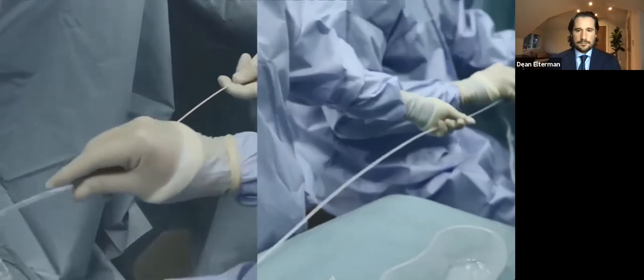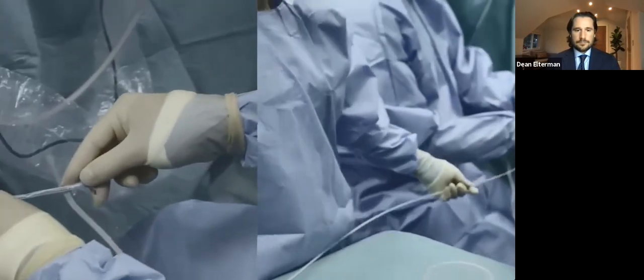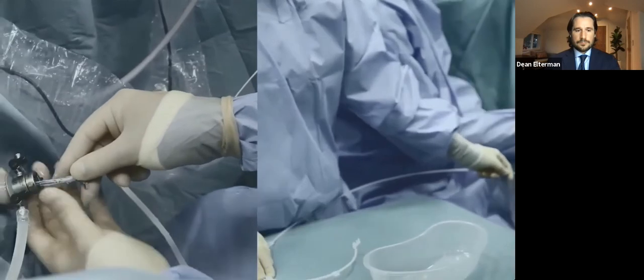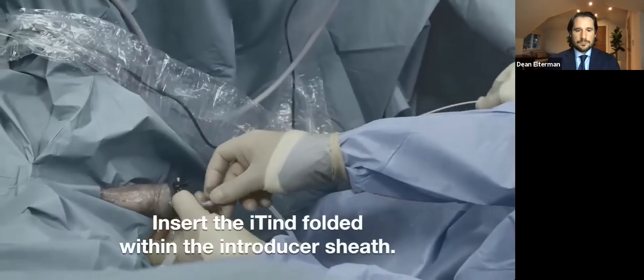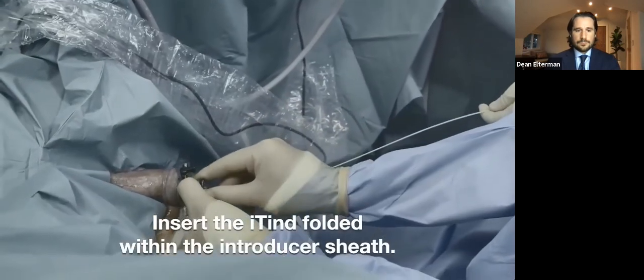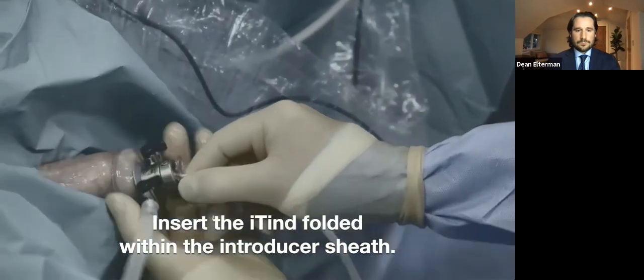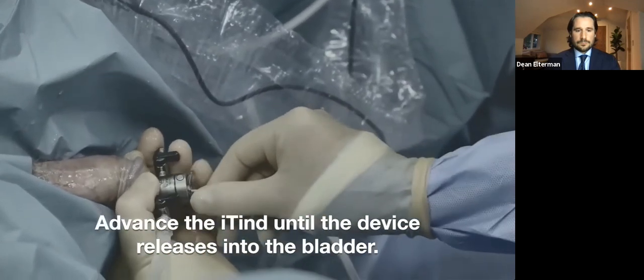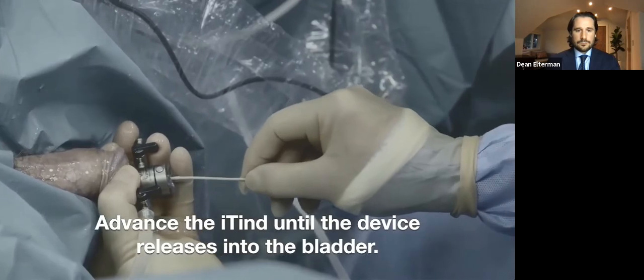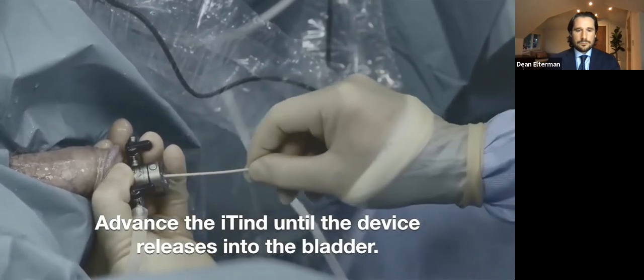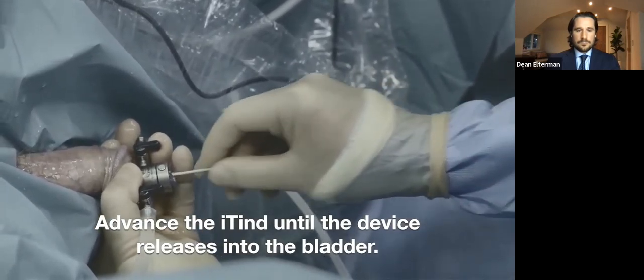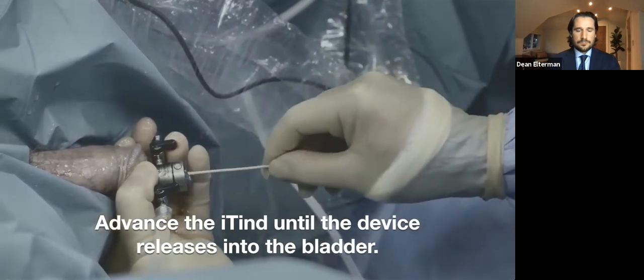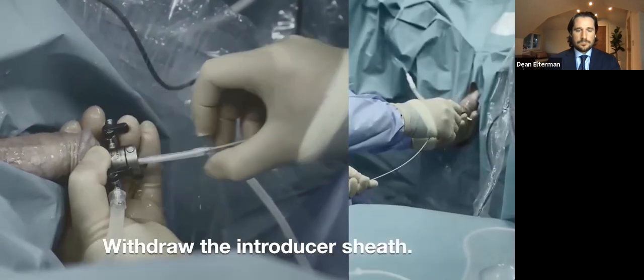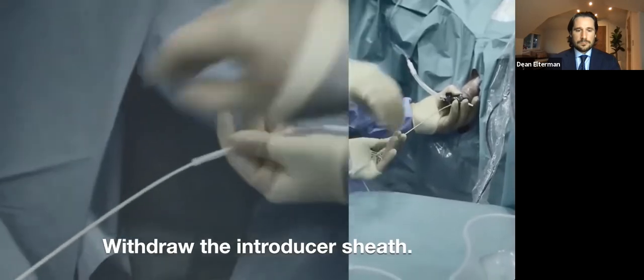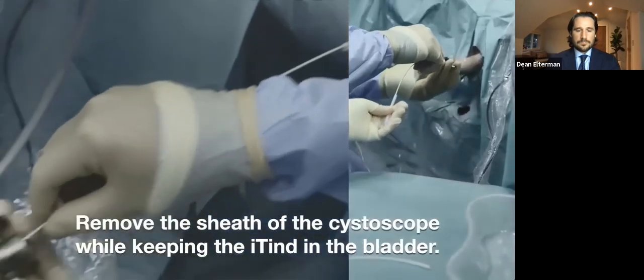The iTind has an outer sheath which keeps it closed. You advance it through the introducer sheath by pressure until the device is pushed all the way through the end of the scope and released into the bladder. At this point you will feel almost an opening or a pop, and you can remove the introducer sheath.